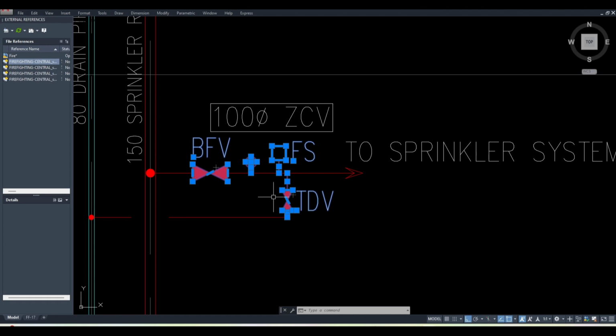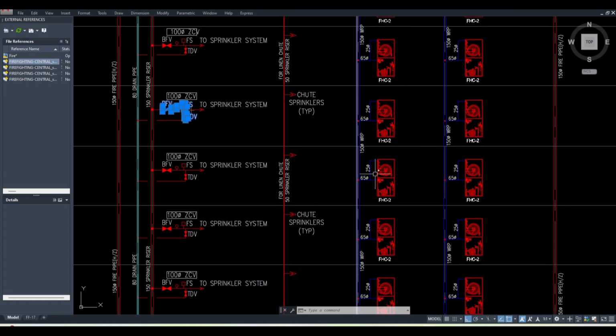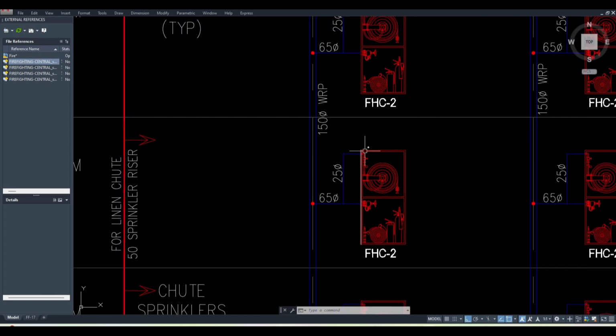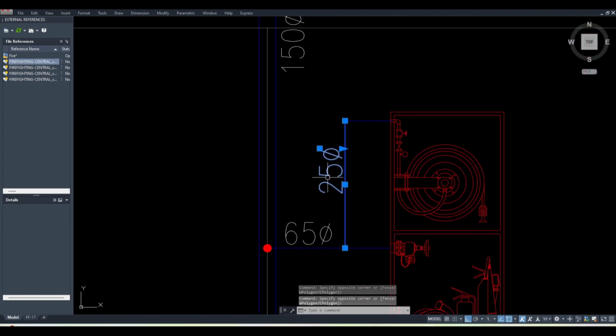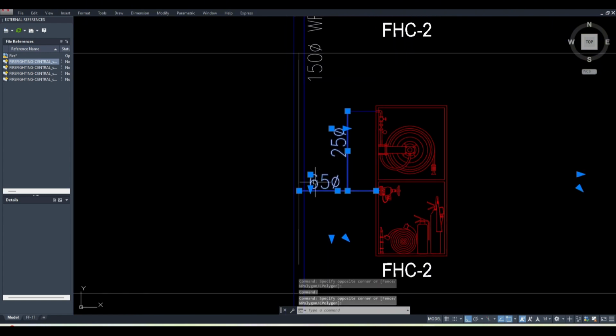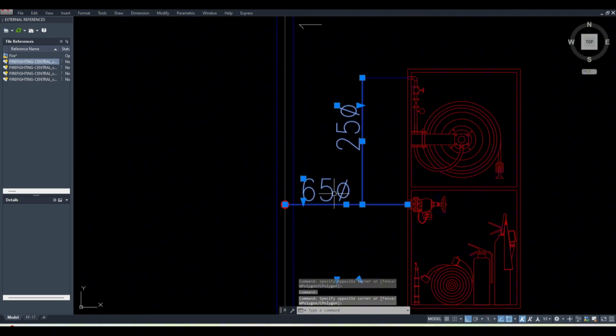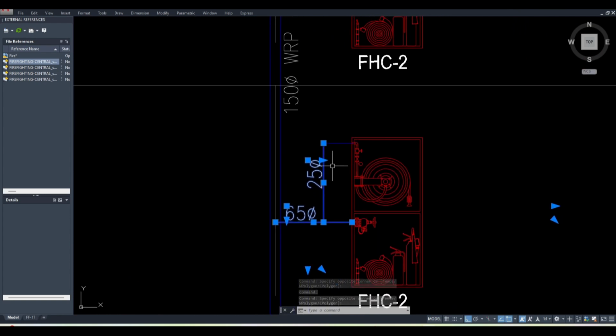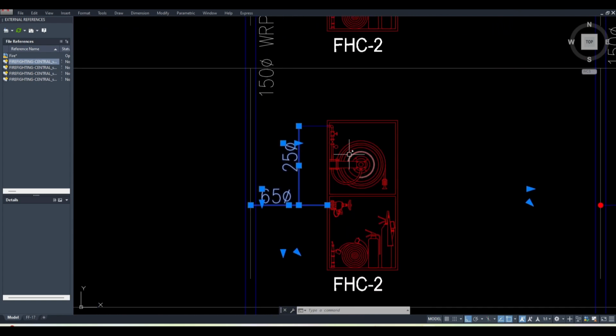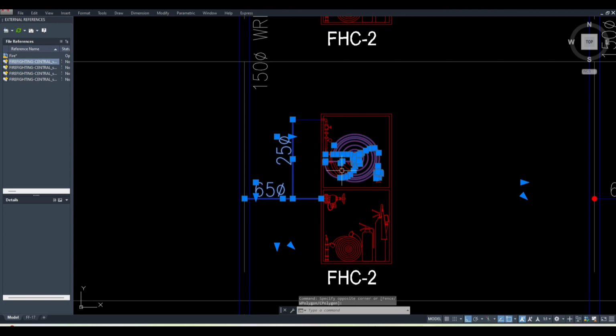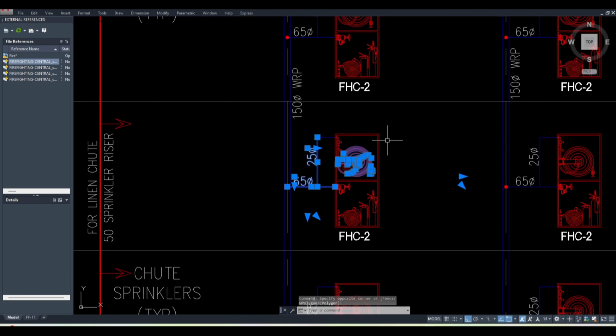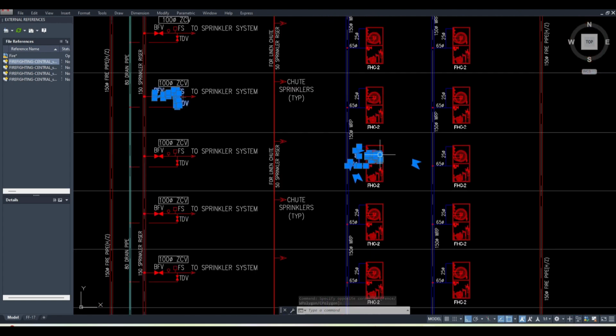So for example, yesterday I told you about the wet riser system. When you go and observe this, it will very quickly come to your mind: okay, this must be 25 mm. If he is using 50 mm, it's wrong. If he is using a 40 mm pipe here, it's wrong, because you know it should be minimum 65. This must be 25. Then this pipe must cover 30 meters. It cannot be more than 6 meters away from the staircase. The distance should be from the door to this fire hose cabinet.